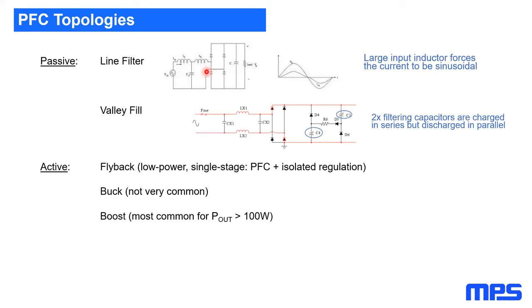Another passive approach is the valley fill circuit. The idea is to split the filtering capacitor placed after the rectifying bridge into two, and with a diode arrangement, charge the capacitors in series from the grid but discharge them in parallel. This enlarges the conduction time of the diode bridge, making the current look less spiky and closer to sinusoidal. It won't bring the power factor to one — at best above 0.7 — but for some applications, especially at light load, this can be acceptable.